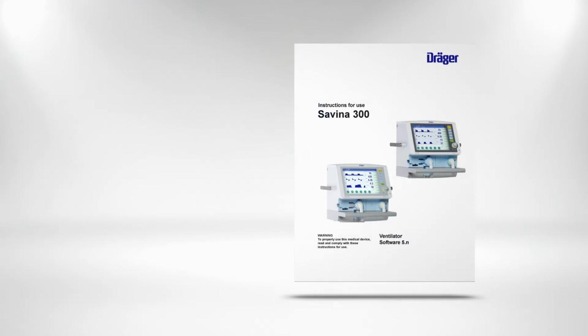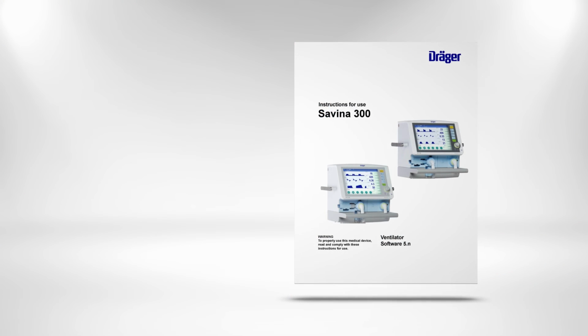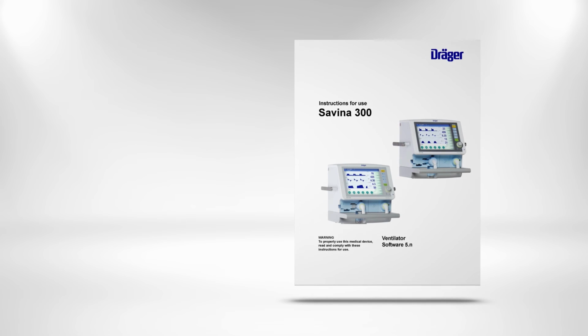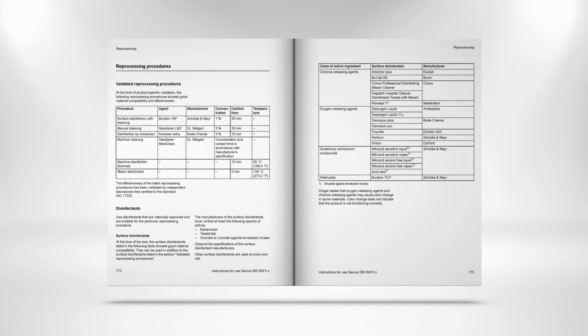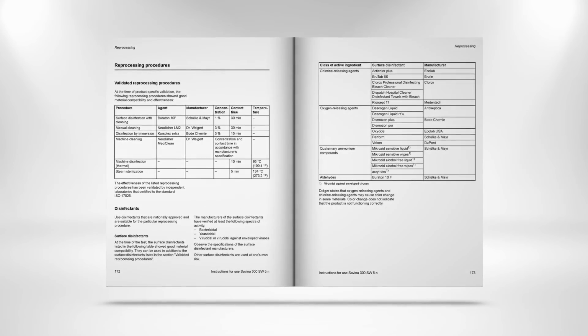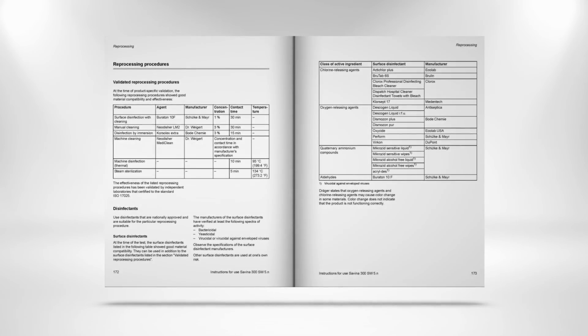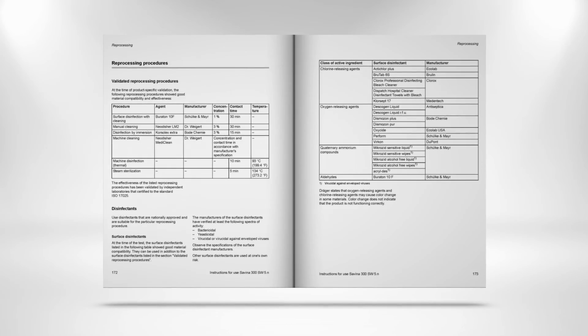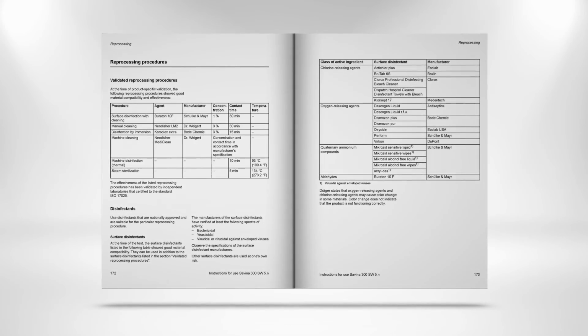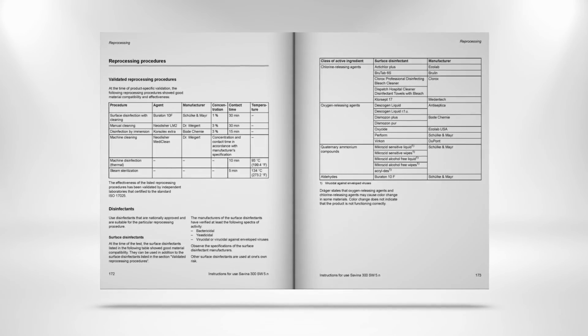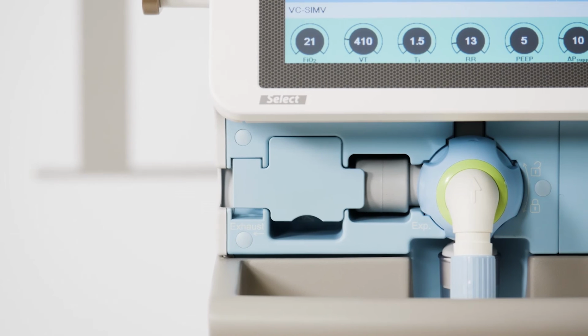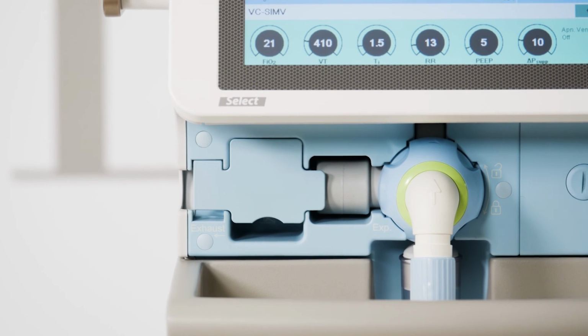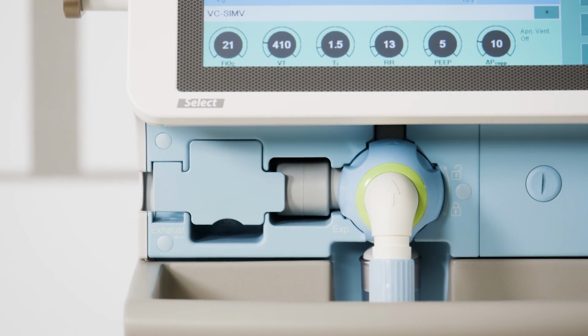If a medication nebulizer was used, dismantle it in accordance with the corresponding instructions for use and reprocess the components in accordance with the reprocessing list for semi-critical medical devices. Reprocess the breathing gas temperature sensor, the reusable CO2 sensor, the breathing hoses, the flow sensor, and the components of the expiratory valve in accordance with the reprocessing list for semi-critical medical devices. Please ensure that there is no residual water in the expiratory valve.